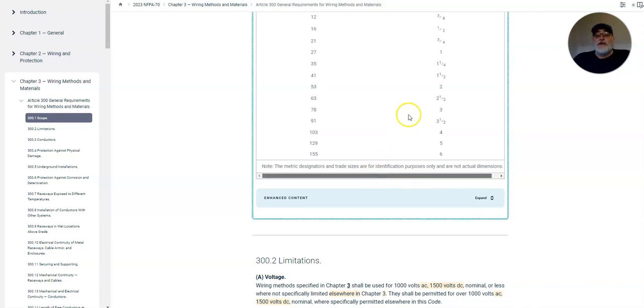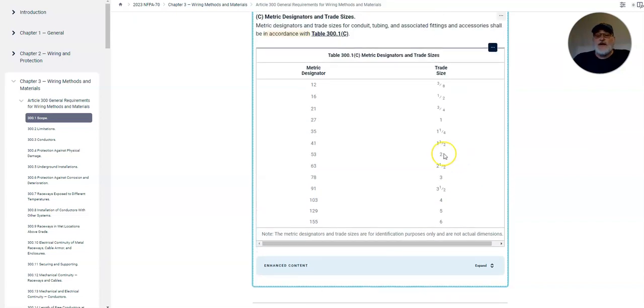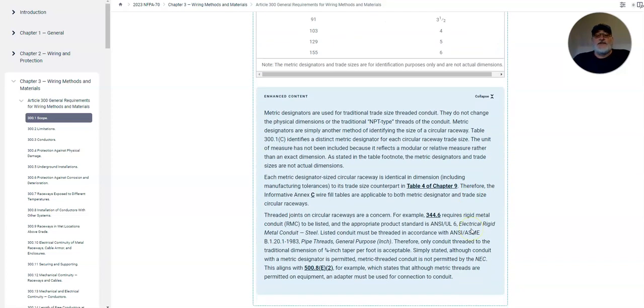Now, mind you, these are metric designators, and the trade sizes are for identification purposes only. They're not the actual dimensions. A 2 inch trade size will actually be just a little bit bigger, okay, as far as the conduit if you're going into a box or into a fitting. Let's see what this says. And I like this enhanced content because it kind of helps me explain to you.